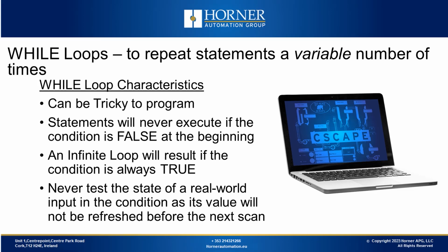Here are some key points about while loops. They can be tricky to program and may lead to infinite loops if not carefully handled. If the initial Boolean condition is false, the statements won't execute, which might not be the desired behavior. Infinite loops are a risk when your Boolean condition is perpetually true, especially when using real-world inputs in the condition. Real-world inputs are updated at the start of a scan, while loops run within the same scan, making it challenging to detect changes in real-world input states within the loop.